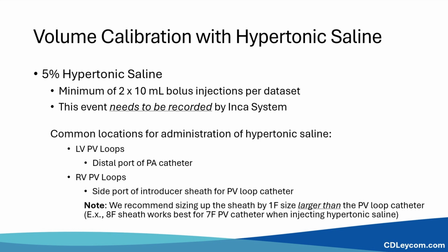For interventions like a TAVR procedure, where the PV loop catheter and TAVR system are both delivered via the same access, one would save recordings into 2 datasets.